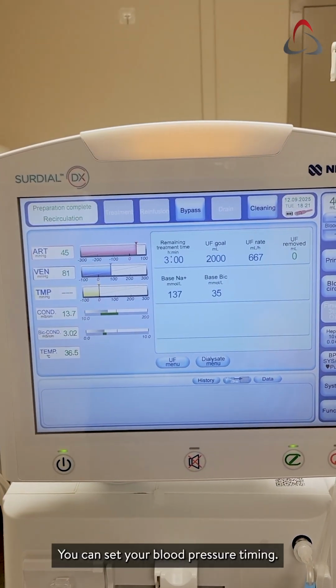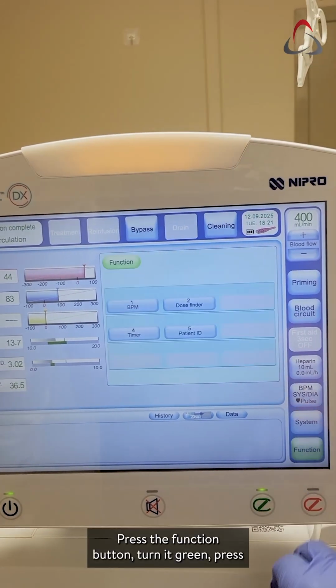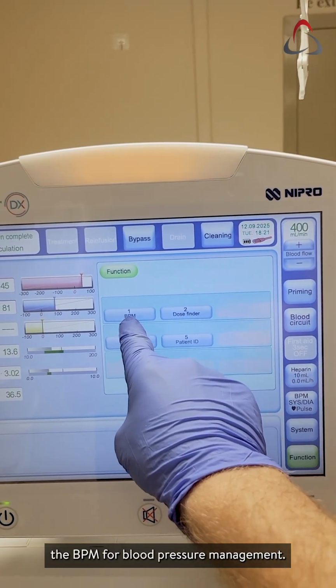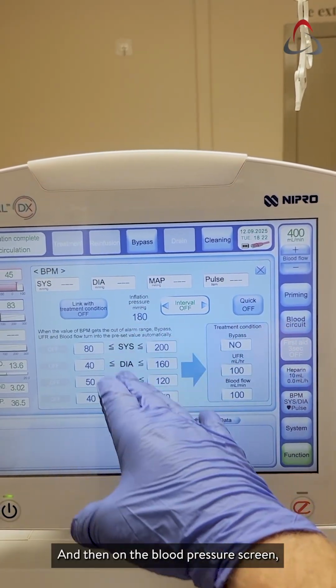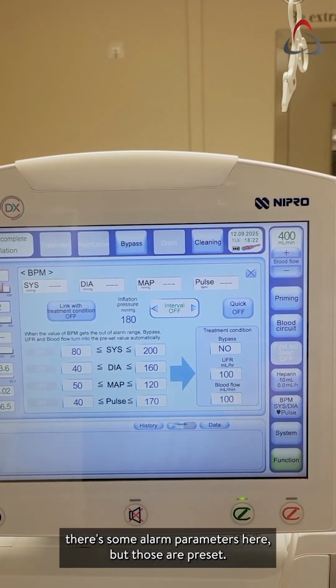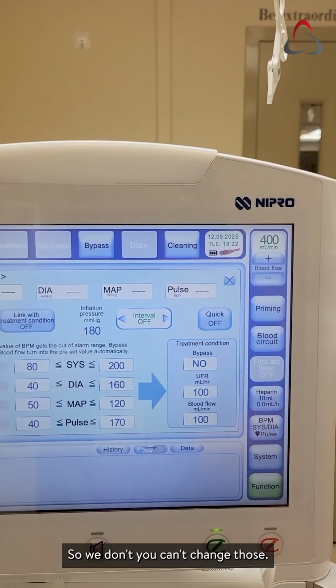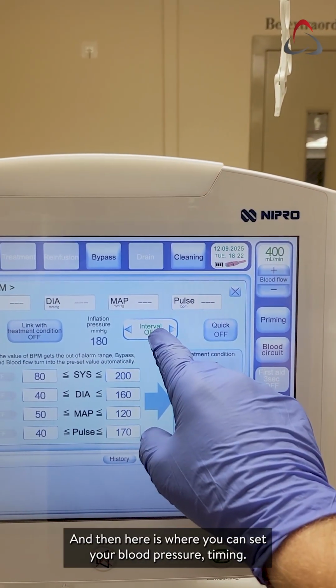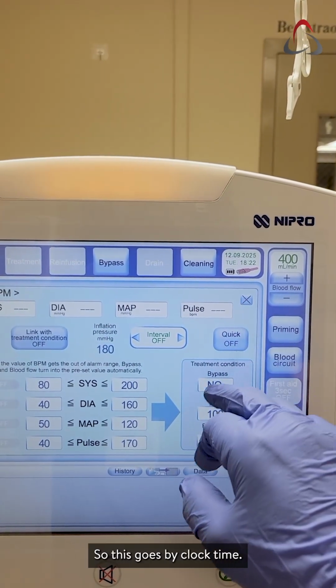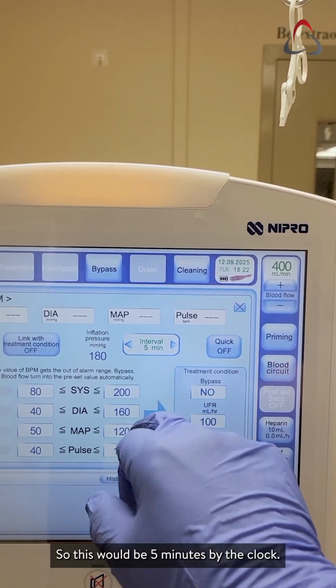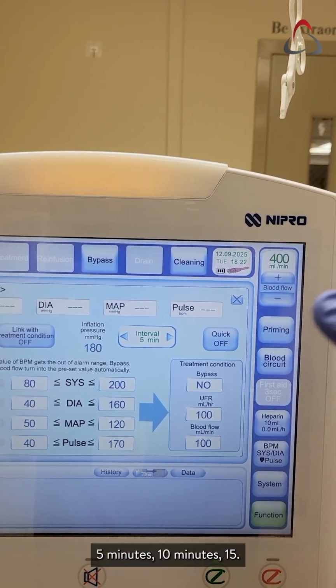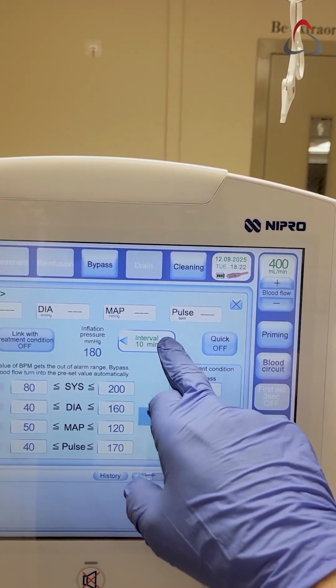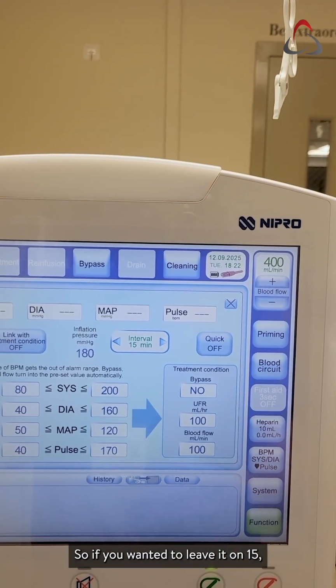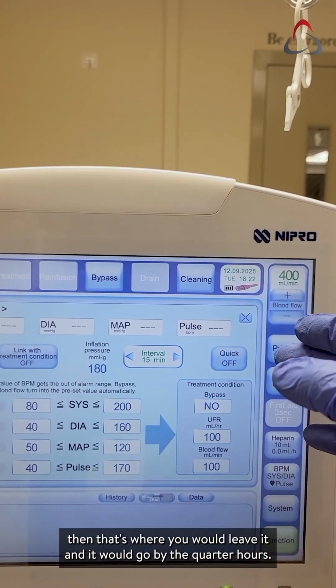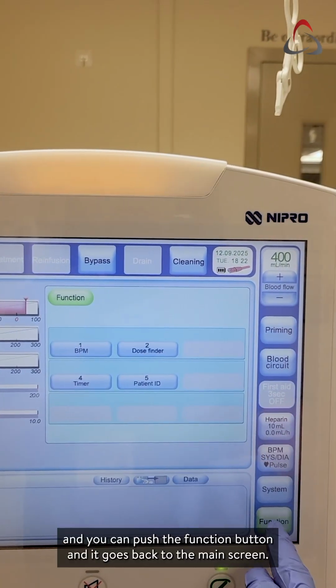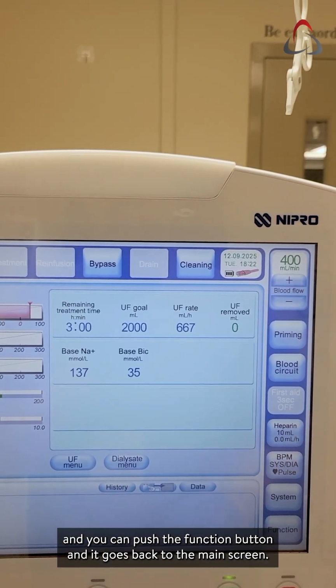You can set your blood pressure timing. Press the function button, turn it green. Press the BPM for blood pressure management. And then on the blood pressure screen, there's some alarm parameters here, but those are preset, so you can't change those. And then here's where you can set your blood pressure timing. So this goes by clock time, and it's side scroll. So this would be 5 minutes by the clock. So it would be at the top of the hour, 5 minutes, 10 minutes, 15. So if you wanted to leave it on 15, then that's where you would leave it. And it would go by the quarter hours, and then just close this menu. And you can push the function button and it goes back to the main screen.